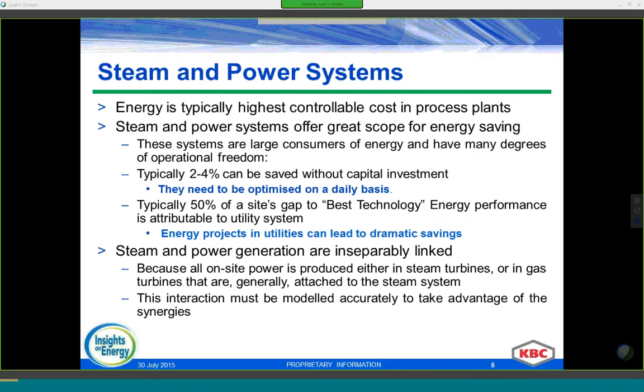The ever-changing demand of steam, supply from different process units, equipment constraints such as maximum and minimum boiler loads and turbine limits, and emission limits — especially if we can burn fuel oil and fuel gas — all affect the way we try to balance our systems. This also offers significant scope for energy savings. Our experience tells us that up to 50% of the total gap compared to best technology can be allocated to steam and power systems. In economic terms, models can typically help identify between 2 to 4% savings without capital investments.